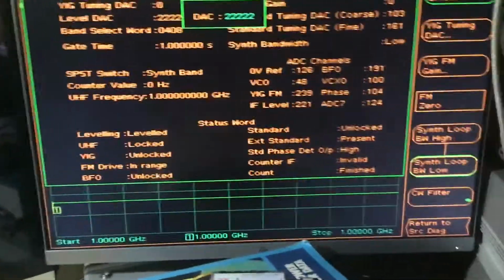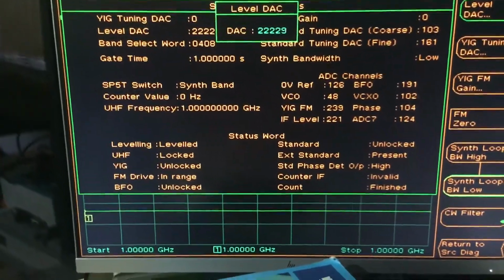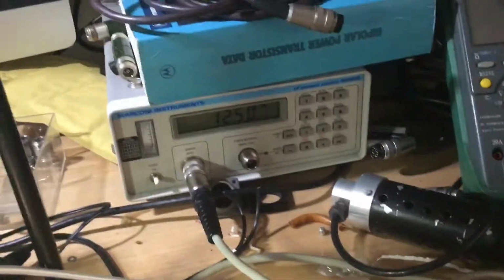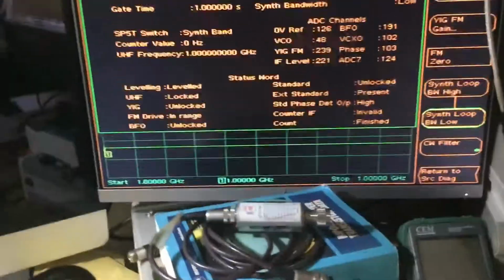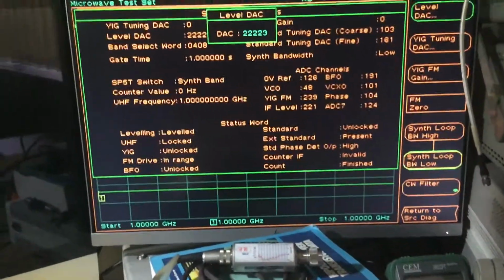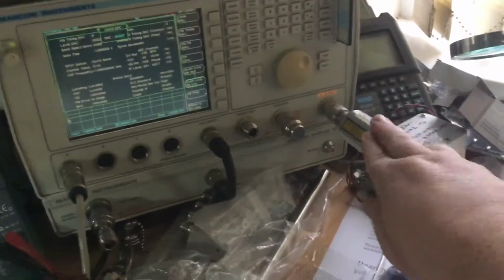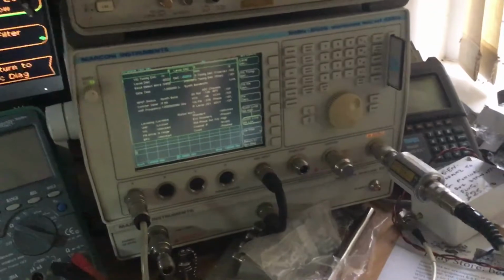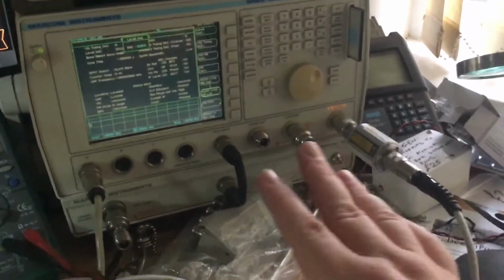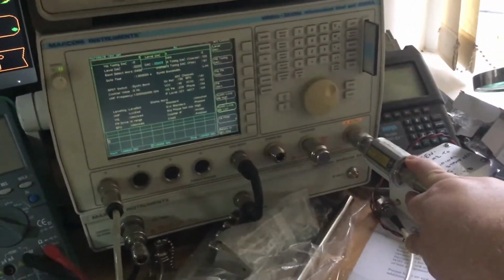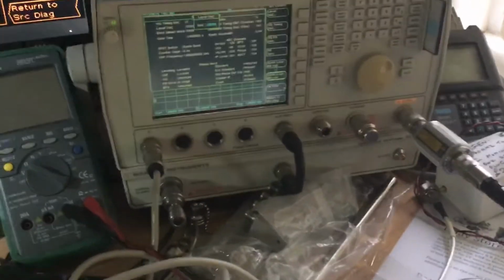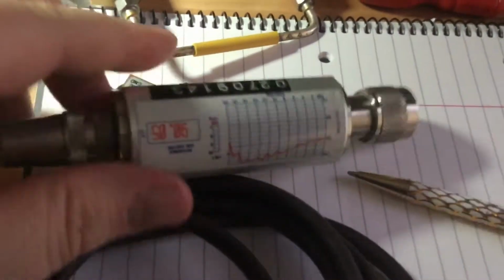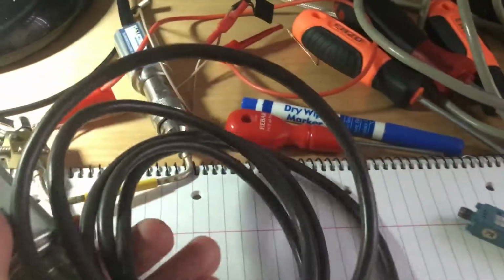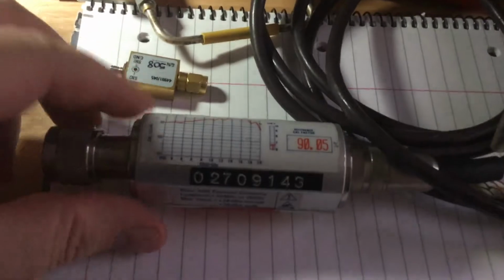By adjusting this level, which is very finely adjusted, it can get a precise level output recorded within its own memory and then progress throughout the frequency range. It does that by sensing what's coming back, as per this calibrations routine, using this power sensor, and it does it itself in a loop mode. Obviously that calibration is only as good as the calibration on the power sensor, so it's very important that the calibration data held on the sensor is inputted within the menu, on the calibration side of things.